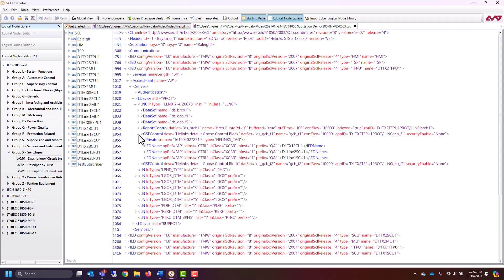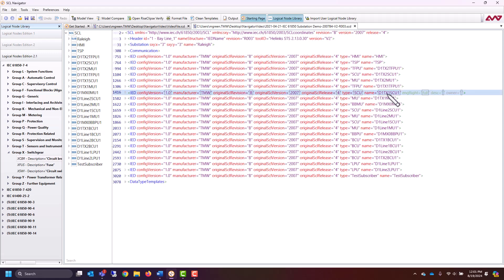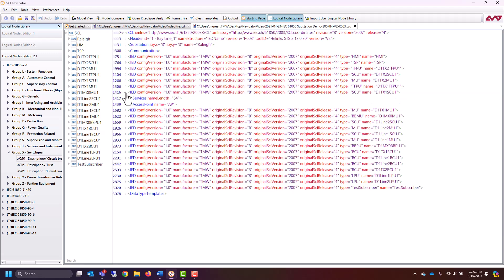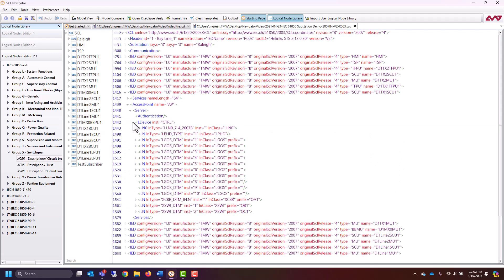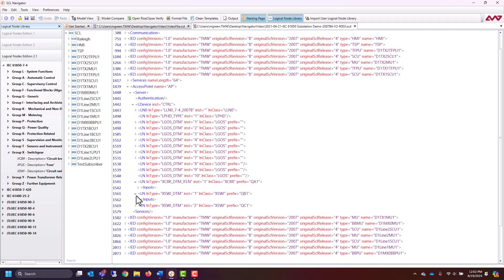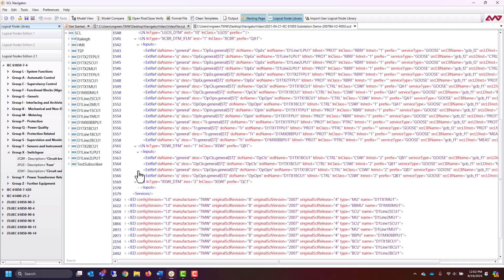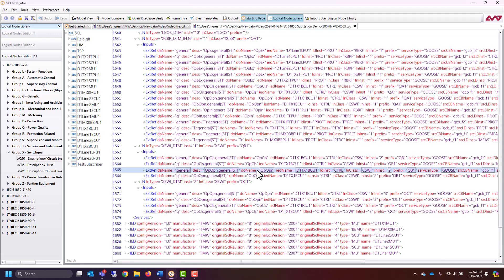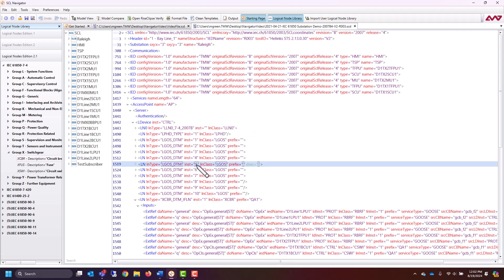If we go into the GOOSE, we can see all of the IEDs that are subscribed to it — D1, TX1, SCU1. So I can go all the way back to the top, find D1_TX1_SCU1, open that up, go down to the access point, open the server. There's a control logical device in here, and you can see all of the logical nodes. Opening each of these logical nodes, we can see there are different inputs from not only that one GOOSE control block, but all the other GOOSE control blocks it may need to subscribe to in order to get the data it needs for its protections. That's one way you can see how data will flow around your device.